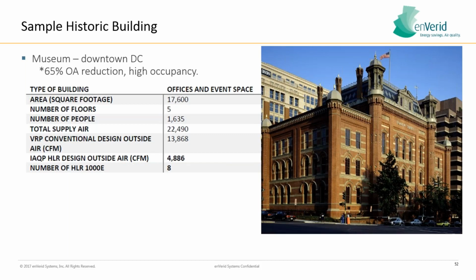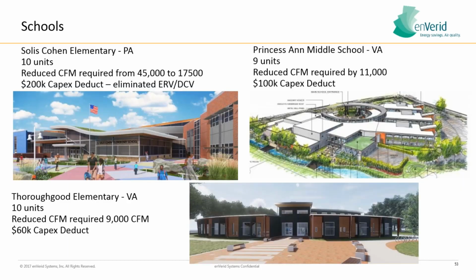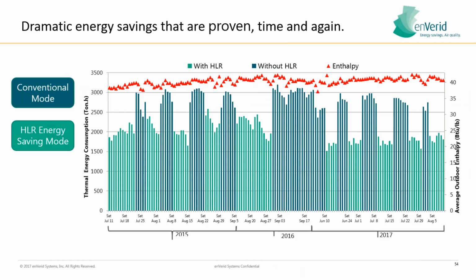So that's a big concern, right? Especially amongst architects, is adding enVerid going to increase the dimensional size of my mechanical room? And in many cases, it does not. On a retrofit, obviously, you might have to suspend it from the ceiling, put it on top of an air handler, get a little more creative with it. You can even place it directly in the space. So here's a variety of other schools in a variety of climate zones, Pennsylvania, Virginia, et cetera.